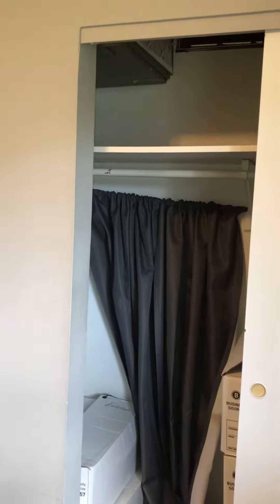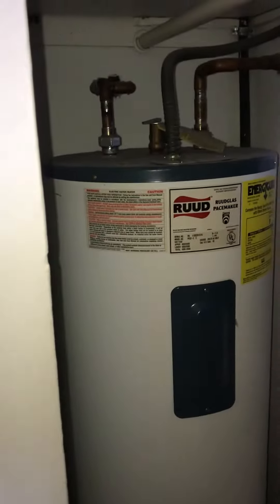We've got a closet situation. The air handler is fastened to the ceiling, so that's not going to work. I talked to the homeowner and made a note that the shelf needs to come out. We're going to mount the new air handler on that stud, basically right in here. We've got the water heater — eventually at some point it'll need to come out, but a shorter unit can go in.